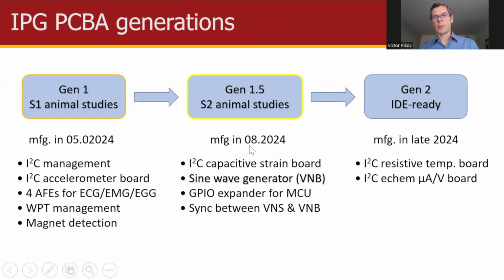The next generation will come a little bit later, just 3 months later. And this will have some additional boards, such as a capacitive strain board. Again, it's an external board plugged into the header. And on the IPG board, we will have the sine wave generator for vagal nerve block. In order for this sine wave generator to properly function, it has to be synchronized with the vagal nerve stimulation channel. And in order to do that, we actually need to increase the number of GPIO pins we have, because we're running out of those on the MCU. So we'll have an IO expander added, and we'll enable the circuitry for syncing these two channels in order to have a proper unidirectional block.